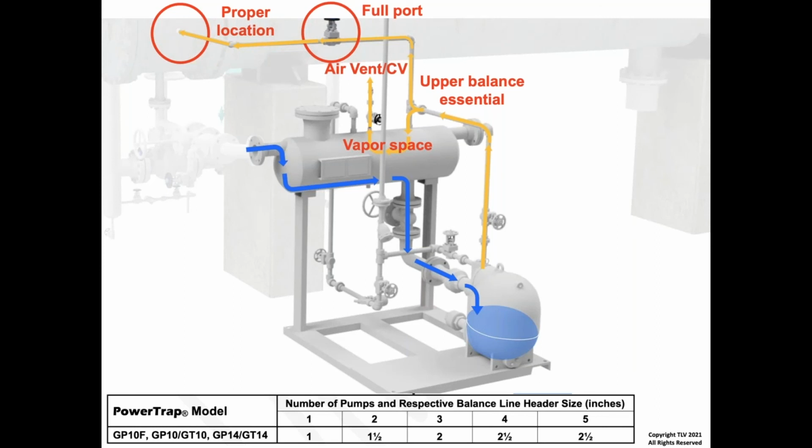Here we go. So if you look at the bottom chart, if you have a 1-inch tap at that proper location, you can work with one pump. Sometimes we see something like a 3/4 inch tapping. That's really not big enough. That's a restriction. But if you've got to use 2, 3, 4, or 5 secondary pressure drainers, do you see that that tapping needs to be 2.5 inch, or in your case, maybe 3 inch, because you like to use 3 inch instead of 2.5 inch.